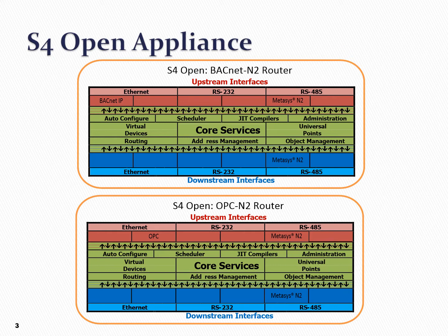The upstream and downstream terminology relates to where the Metasys components sit relative to the N2 router. A downstream N2 interface faces the N2 bus and its field devices. An upstream N2 interface faces the Metasys supervisor controller and enables coexistence with the supervisor controller.